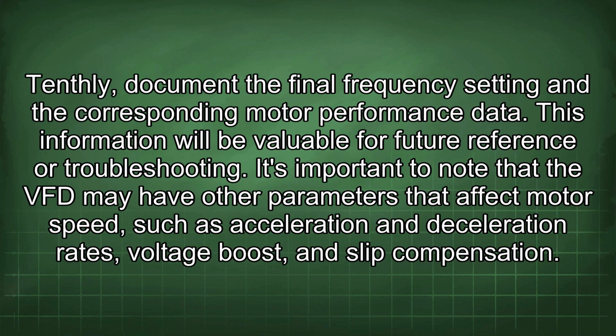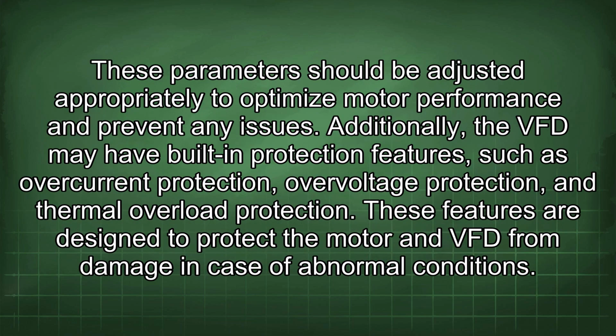It's important to note that the VFD may have other parameters that affect motor speed, such as acceleration and deceleration rates, voltage boost, and slip compensation. These parameters should be adjusted appropriately to optimize motor performance and prevent any issues. Additionally, the VFD may have built-in protection features, such as overcurrent protection, overvoltage protection, and thermal overload protection. These features are designed to protect the motor and VFD from damage in case of abnormal conditions.